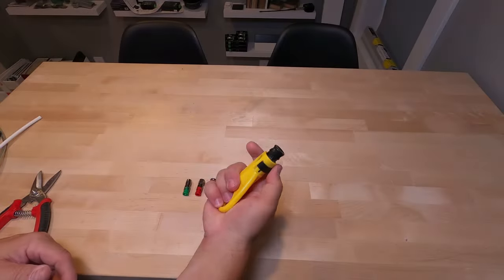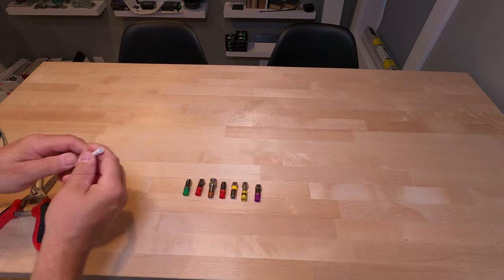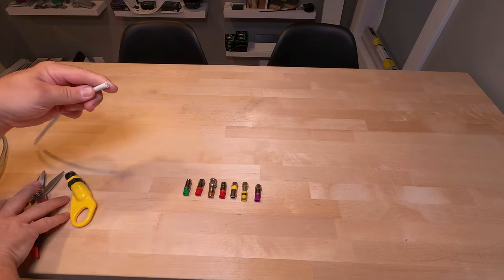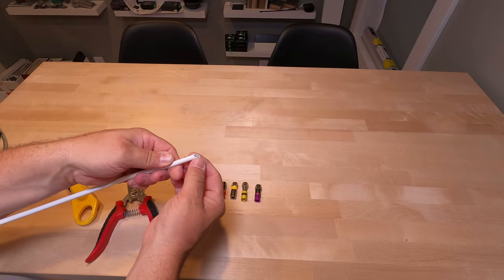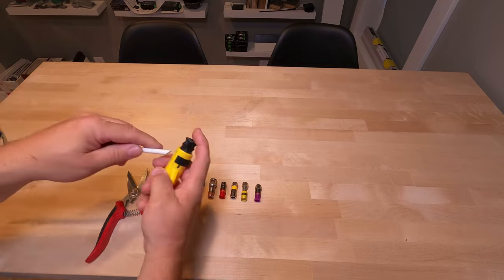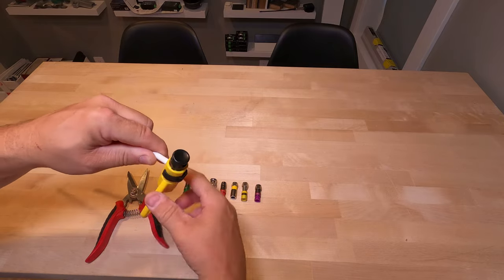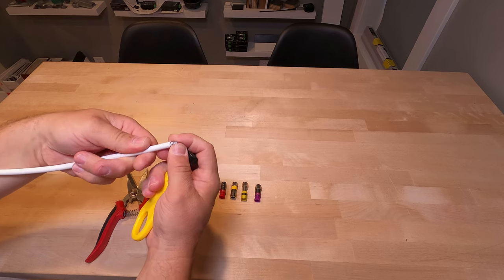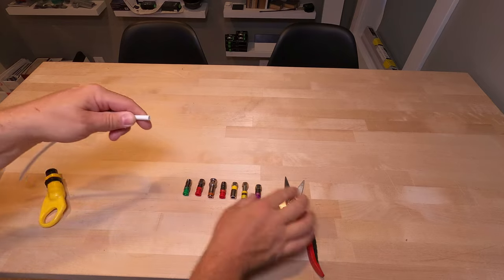So what I'm going to go over here is just a couple quick things - make sure there's no mistake. I'm actually gonna cut one of these wrong and show you what it does to the cable stripper tool. So I cut that at a 45, probably a 40 degree angle, and then as you watch me try to run my tool around this, you can see it's kind of wobbly and it just didn't get a full connection. It didn't cut off the dielectric from, didn't remove it from the copper.